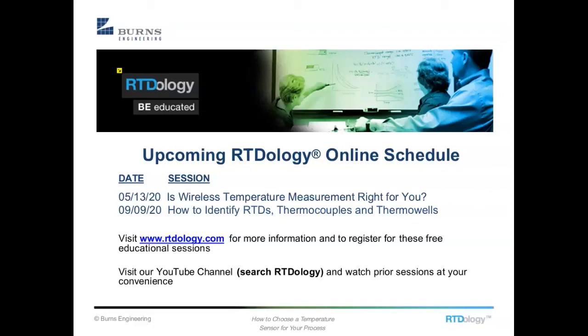A couple of questions have come up from some folks on the session. What is the temperature compensation factor for the thermowell? Well, I'm not exactly sure what that is referring to, but I would guess that we're just looking at an error due to the immersion length, and it varies a lot based on the flow rate and the material that's in the piping. Actually, the material of the thermowell can be a factor there, and also the ambient conditions. Stem conduction can be affected by things like a fan blowing on the outside of the temperature measurement point. The sun shining on it is another source of error. There's just a lot of things like that. I think that's what that question is referring to.